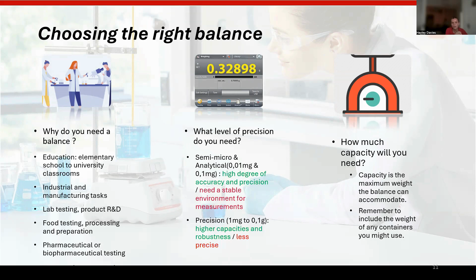No problem. And the next question you need to think about is how much capacity you need. We mentioned the maximum capacity of the balance. You need to remember to include the weight of any containers that you might be using, because the maximum capacity will include the weight of your weighing container as well. So just bear that in mind. If you've got a 120 gram balance and you've got a glass container that you want to weigh into, it's probably not going to be suitable. So you would just need to think about that.